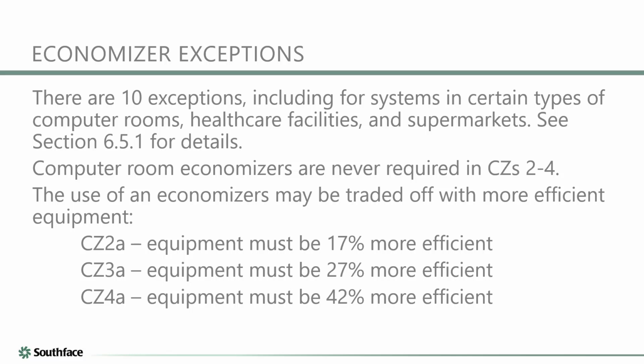Do we want to spend money on economizer function and controls, because by shutting the equipment off and using the economizer function, we increase efficiency? Or do we want to just increase efficiency in the performance of the equipment, because there's less complicated controls required for that, less sequencing, less stuff to go wrong in some ways, and you simply put in a more efficient piece of equipment to gain that efficiency you're looking for?